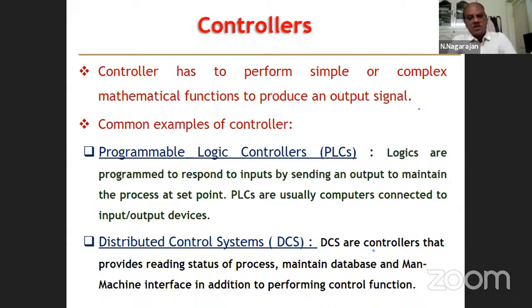Another important control system is the distributed control system, which is very widely used in all the process industries. DCS are controllers that provide reading status of process, maintain database, and man-machine interface. PLC is one small piece of device which is controlling a particular parameter. If you have 1,000 parameters in the plant, you will have 1,000 PLCs. But DCS is the overall thing which takes care of the complete control of the plant, and it is a large database.